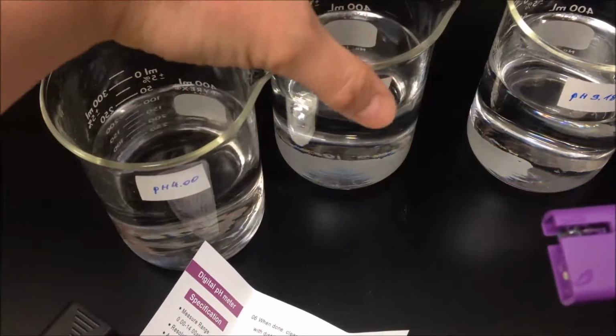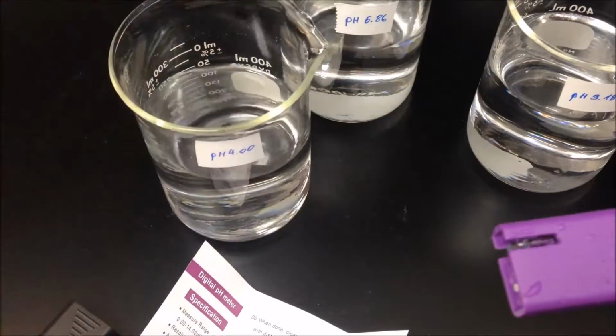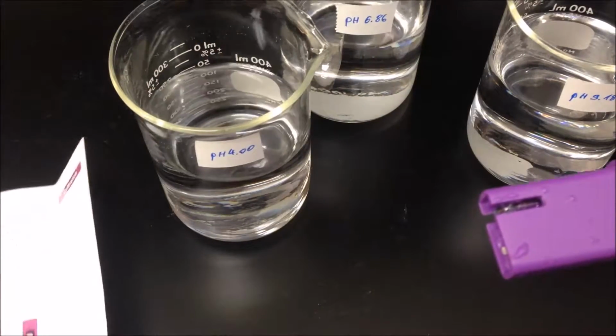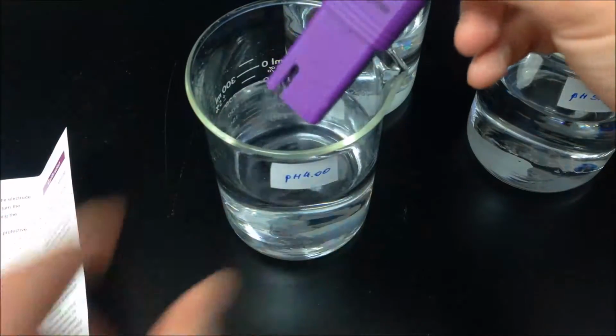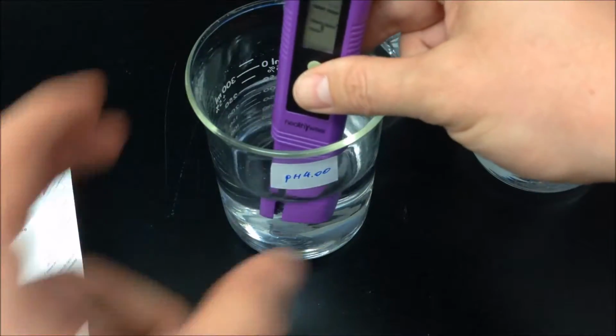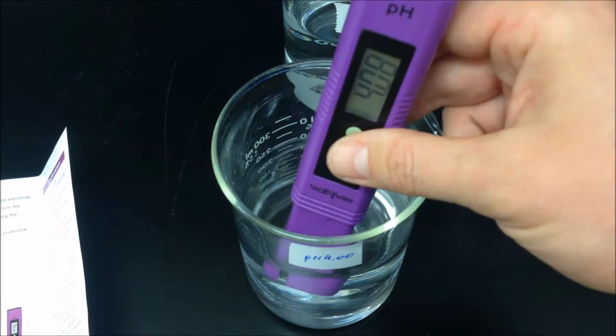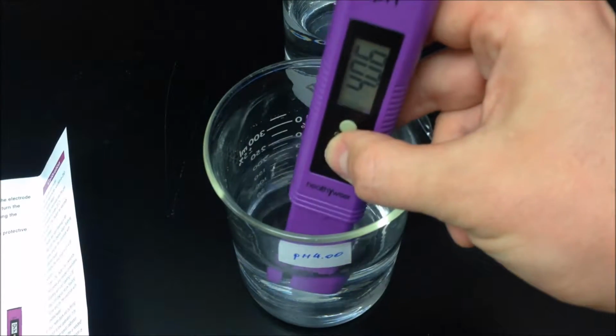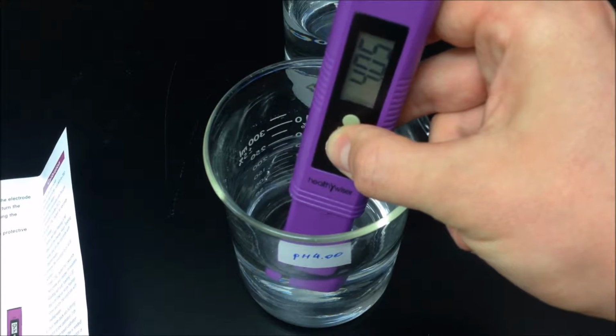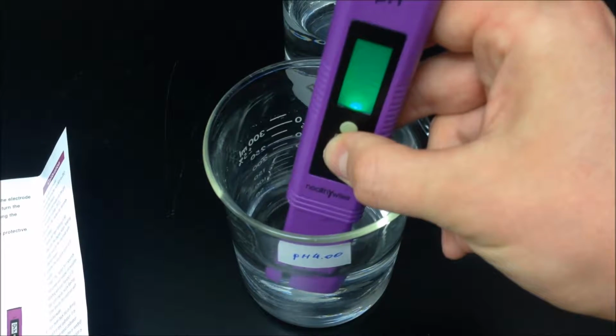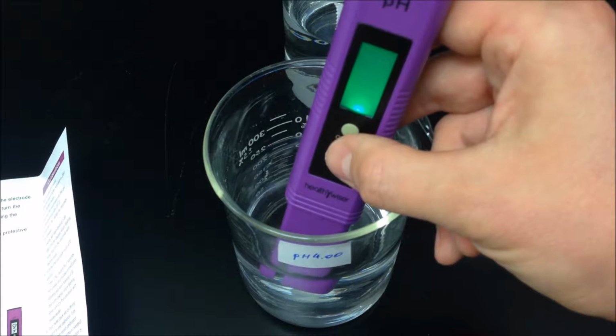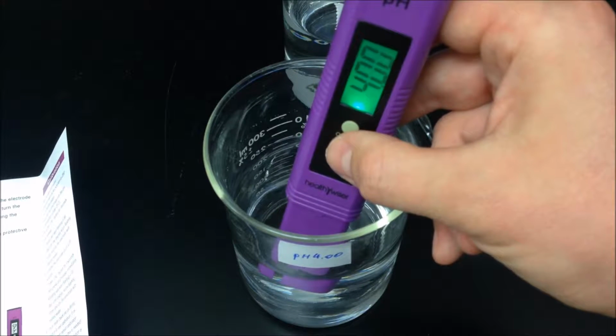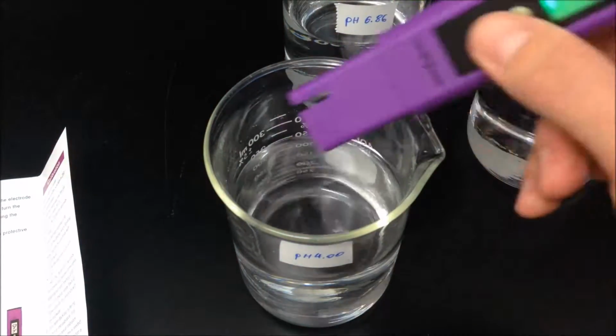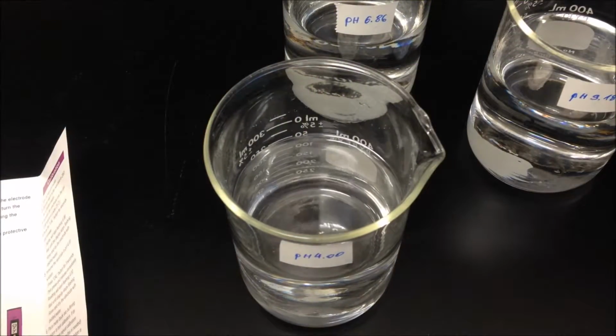So now we go to the second buffer solution as it's shown in the manual. So I'll put this here on the side, and also here we'll put our pH meter in, and I will again push the calibration button for 3 seconds. I'll release it, and then I have to push one more time, and you can see the pH 4 is flashing. Alright, now it's stopped. I will take it out and I rinse it quickly.